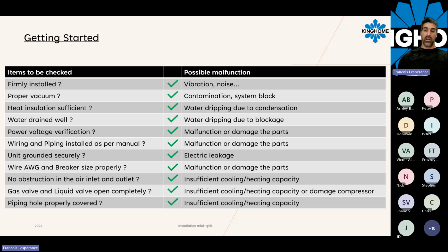So we can feel the cold temperature flowing from the hole, and it had some impact on the return air sensor. The return air sensor is always sensing that it was cold, so the unit is always overshooting to maintain the temperature in the room. So sometimes little stuff like that can bring some service calls. So you have to have an open mind, make sure you have checked everything to make sure everything is working properly.